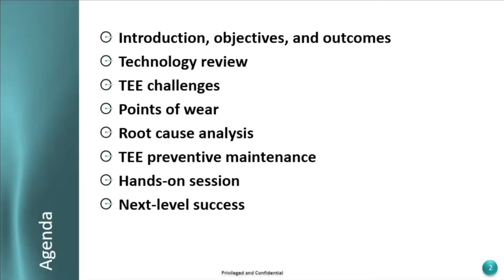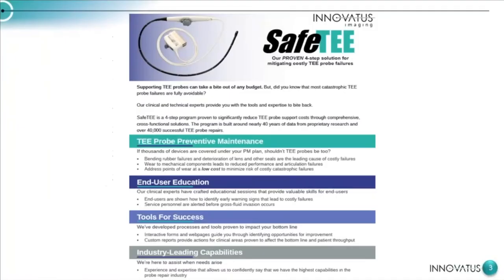So we're going to talk about our objectives and outcomes. We're going to do a technology review of the probe itself. I have six probes here we're going to do preventative maintenance on. We're going to do a mock preventative maintenance, and these probes are pre-damaged. These are probes that we got in for repair that are catastrophically damaged, and each one has a little bit different damage that we'll take a look at. So this will be live. Some of the challenges of TEE probes, points of wear, and these probes have been disinfected, so don't worry about handling them. We're going to talk about root cause analysis, actual preventative maintenance on the TEE probes. We're going to do the hands-on session, and then we'll talk about next level success, so where can we take this to the next level in order to prevent TEE damage.